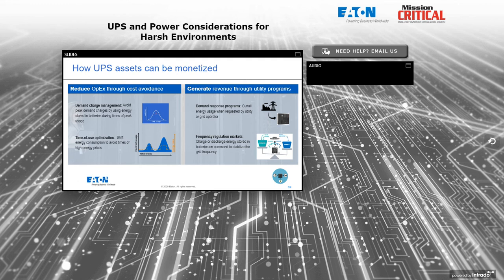So what we're talking about here is the ability to use a UPS and typically a lithium battery to reduce my operation expenses through cost avoidance. Do things like you can see on the left-hand side of this slide, do peak shaving at particular times of day. What we're talking about is slowly discharging the extra battery capacity that I might have in that UPS and utilizing the extra kilowatt capacity to basically reduce the demand that I draw from incoming utility power. Now, this does not mean that we would discharge the battery below what we need to support the critical load for X number of minutes. But it does mean I'm using the UPS's battery capacity and kilowatt capacity when available to help decrease the amount of power that I have to pay for from the utility company.